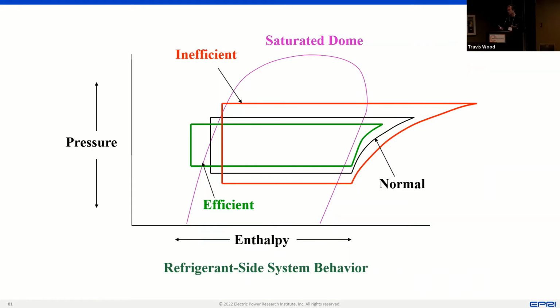So when it's 50 degrees outside and you want to use your heat pump to heat your house up to 73, that's relatively easy - you can do it with pretty high efficiency. If it's 0 degrees outside and you'd like to heat your hydronically heated building, providing 150 degree water flowing through the building to provide the heat, that's a very, very big temperature gradient, and that's much harder to do. The ultimate efficiency is lower, and so the actual efficiency is also lower. These subtleties are very, very important when it comes to design of systems.